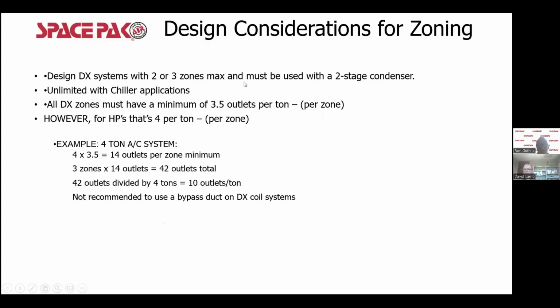All right, so here's the equation. You need to do 3.5 outlets per ton per zone. Okay, so this is on an air conditioning. So for heat pumps, that's 4 outlets per ton per zone. Now, if you have 2 zones, you're going to have 7 outlets per ton because it's per zone. So the takeaway here is that if you're doing 2 zones and they're the same size, or you can make them the same size, then you're going to have the same amount of outlets.